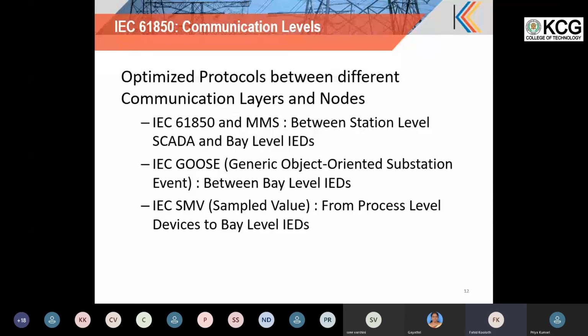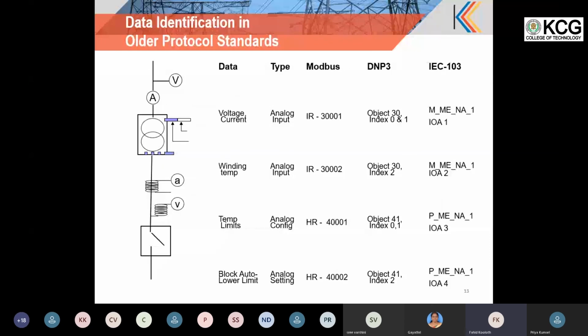Then, as I mentioned, data identification in older protocols uses an IO list for all the protocols. For example, in Modbus, current can be from the 30,001 address; in DNP3 it can be from object 30, index 01; 103 can be with a function name and an information object address. This is dependent on the vendor and changes from one vendor to another in protocols like Modbus, DNP3 or 103, but no stress is given on the data part. There is no data modeling happening. It is vendor specific, and each device can specify where its current, voltage and other values are.